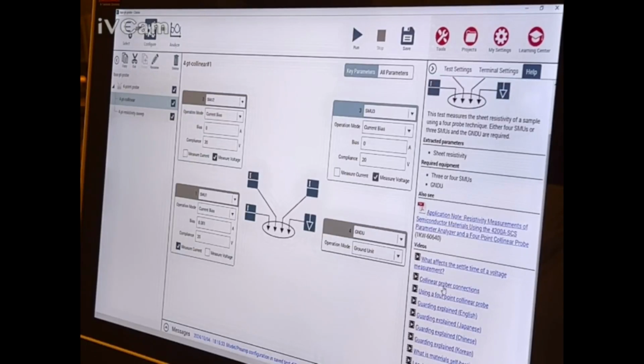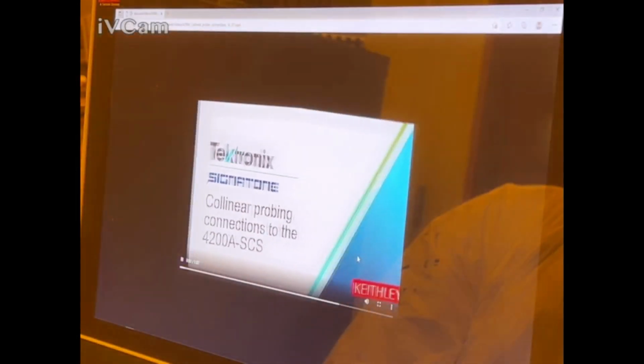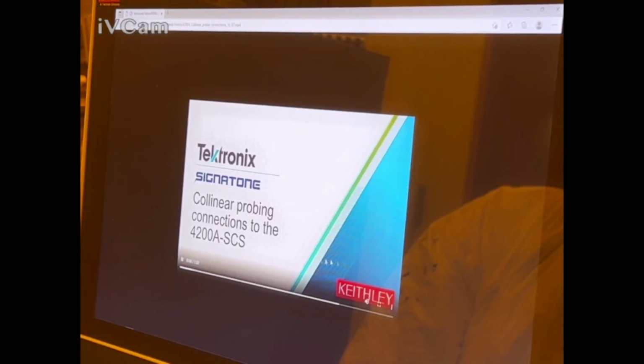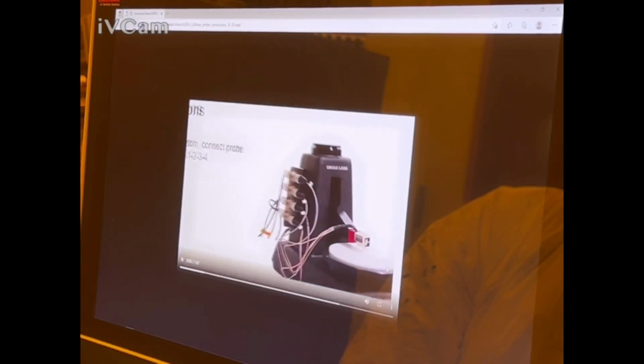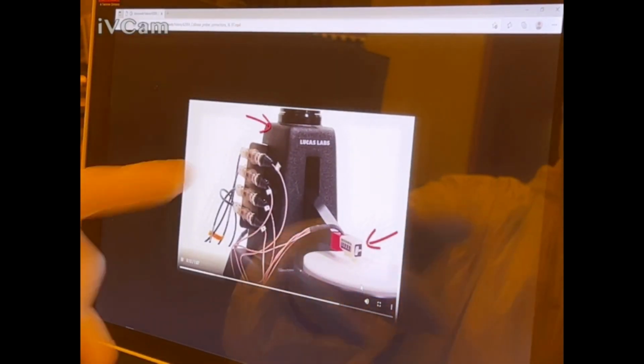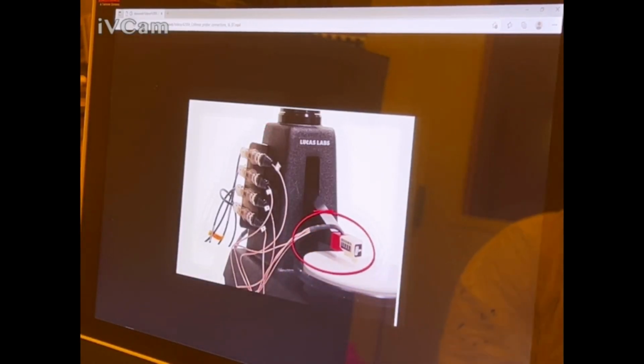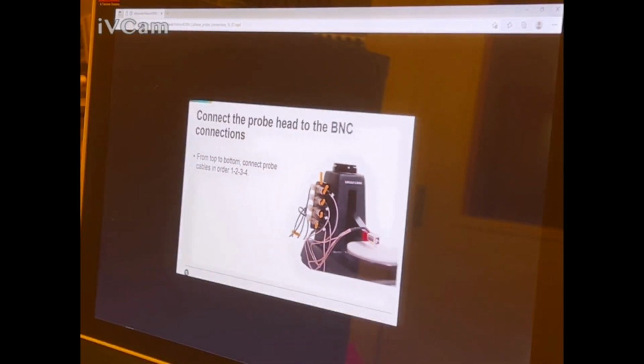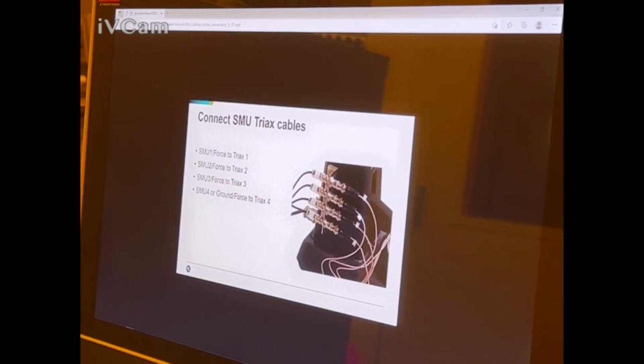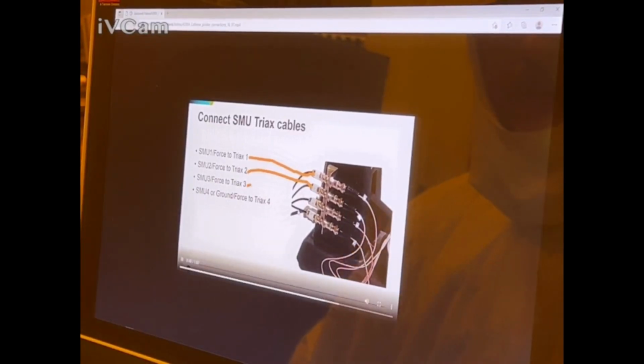So a lot of times, like here, collinear probe connections. If you have a question there, they'll have a video. Connecting the 4200 to the Signatone 302 4-point collinear probe. The 302 probe stand and SP4 probe head has 4 cables that come out of the probe head to connect to this connector panel right here. These probes are labeled 1, 2, 3, 4 and should be connected vertically. Probe 1, 2, 3, and 4. They are then connected to the 4200 SMUs on the force line of each SMU in the same order. SMU 1 to probe 1. SMU 2 to 2, SMU 3.